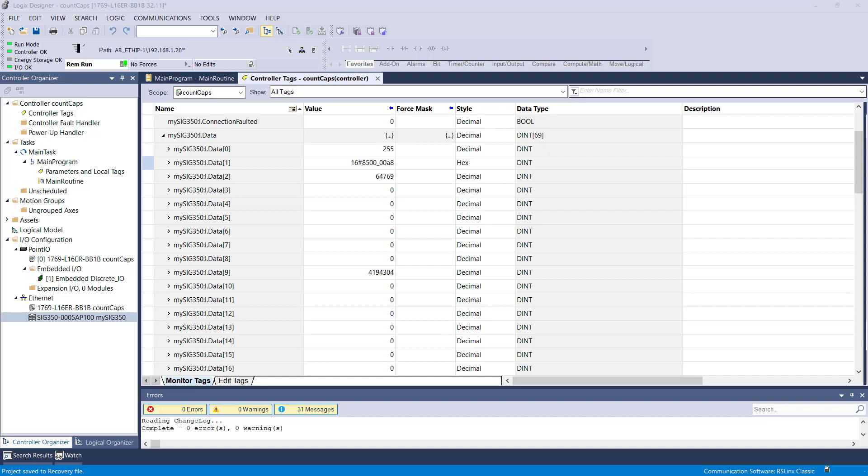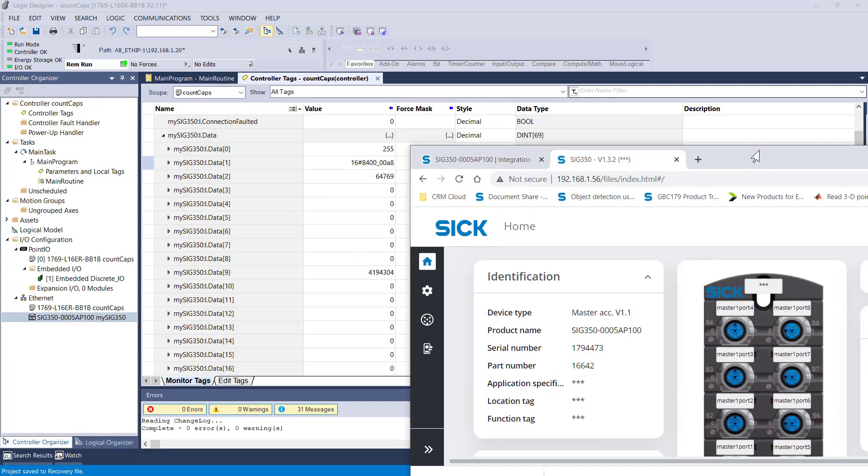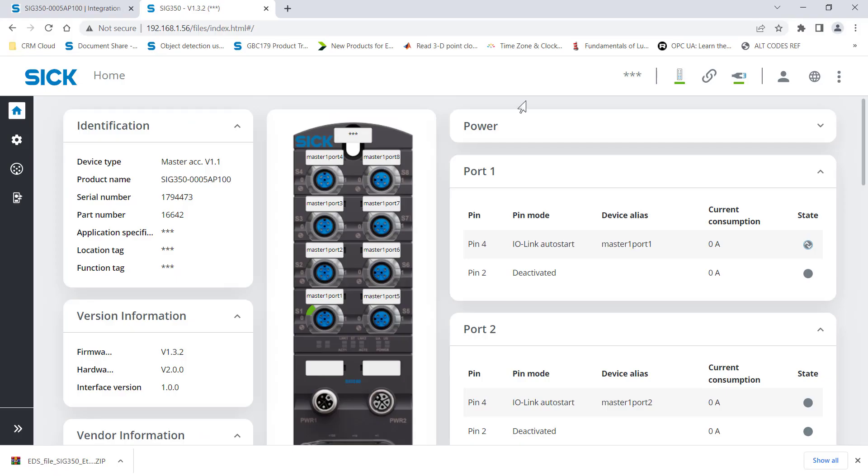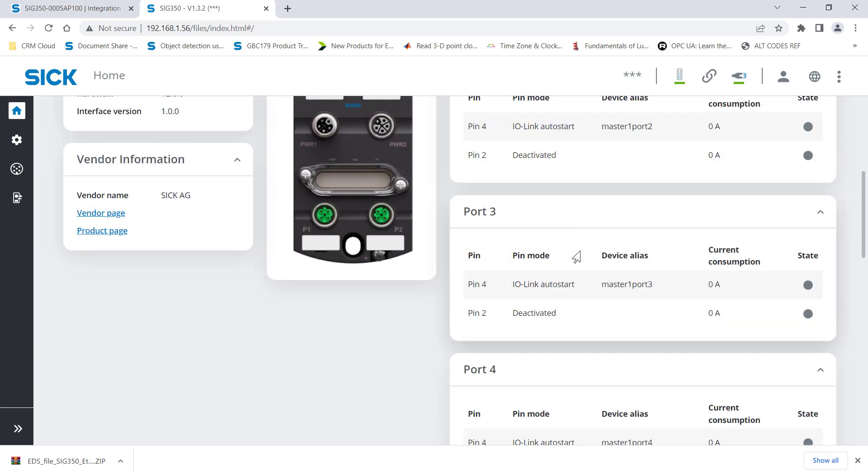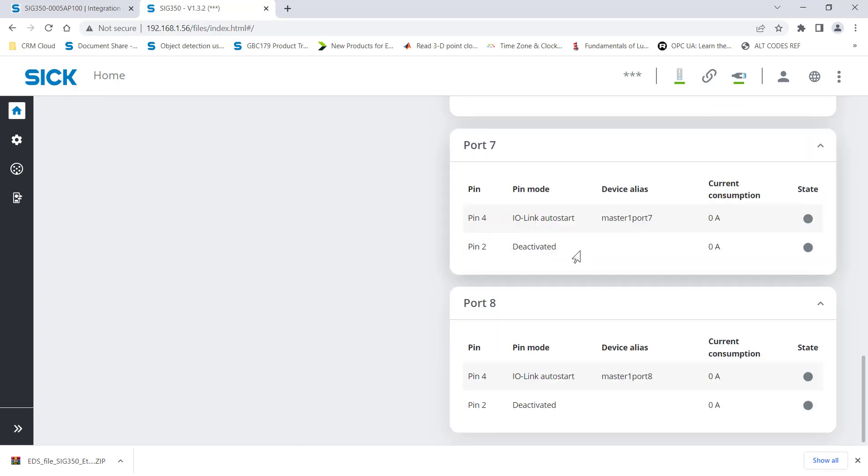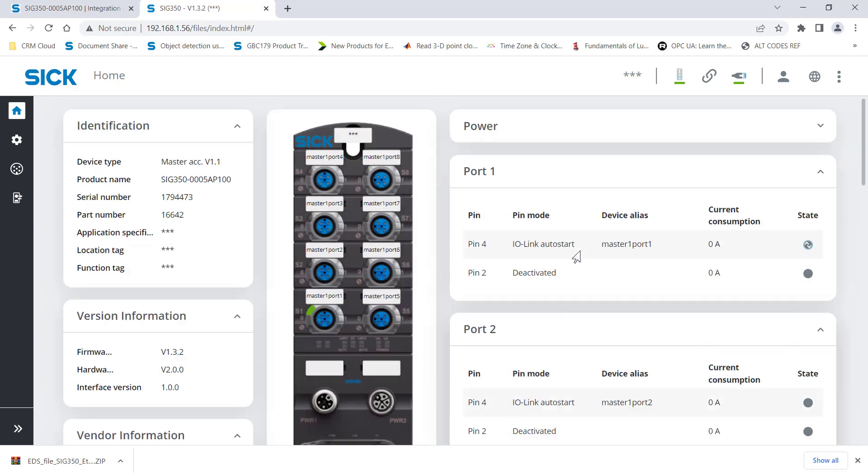So if we take a look at the sensor live using the browser, you can see there the IP address. And then here's the SIG350. So I'm connected directly to the SIG350 over Ethernet. And you can see that there is an IOLINK device online at port one. And in the pictorial there, it's a nice solid green S1.